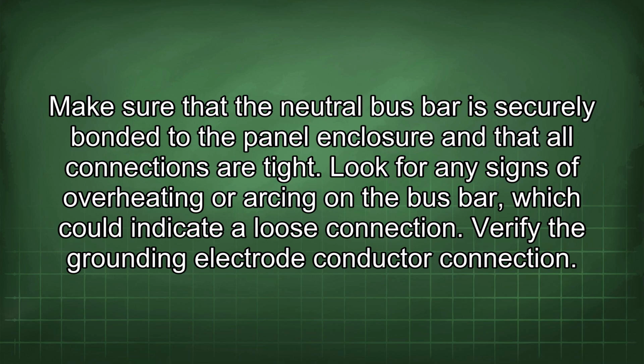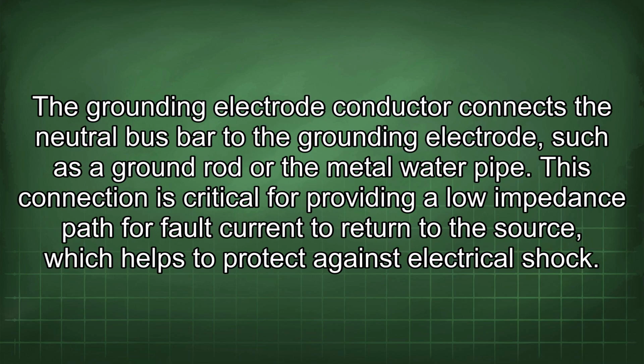Make sure that the neutral bus bar is securely bonded to the panel enclosure and that all connections are tight. Look for any signs of overheating or arcing on the bus bar, which could indicate a loose connection. Verify the grounding electrode conductor connection. The grounding electrode conductor connects the neutral bus bar to the grounding electrode, such as a ground rod or the metal water pipe. This connection is critical for providing a low impedance path for fault current to return to the source, which helps to protect against electrical shock.